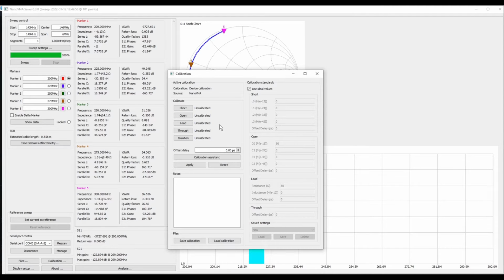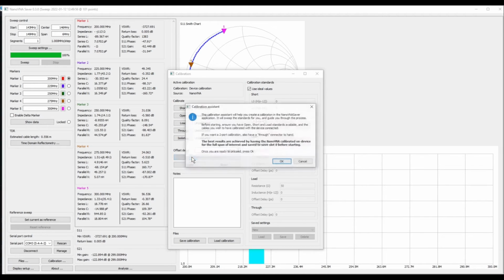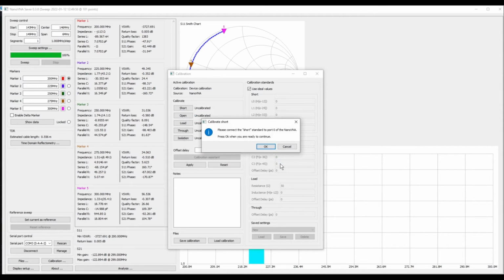So much like we did last time, we're going to run through the calibration, except we are going to do a single port calibration and not a 2-port calibration because we're not doing any through measurements. We're going to use the Calibration Assistant. So I click the button for Calibration Assistant. It says the Calibration Assistant will help you create a calibration in the NanoVNA Saver application. It will sweep the standards for you and guide you through the process. Before starting, ensure you have your open, short, and load standards available and the cables if you wish to have it calibrated with the device connected. It says if you want to do a 2-port calibration, also have the through connector to hand. We are not going to do that as mentioned. So I'm going to click OK, which is going to proceed.